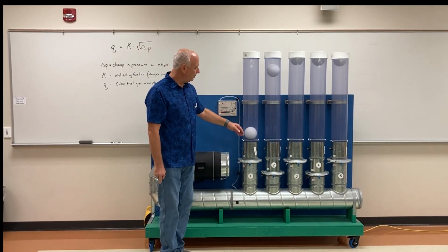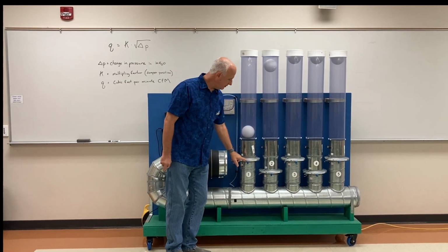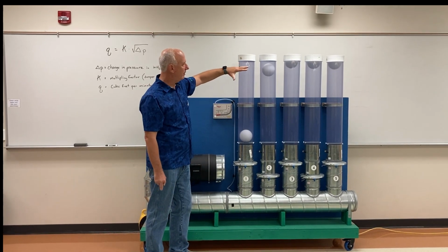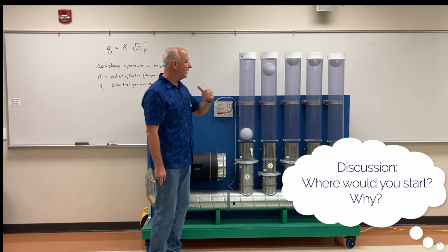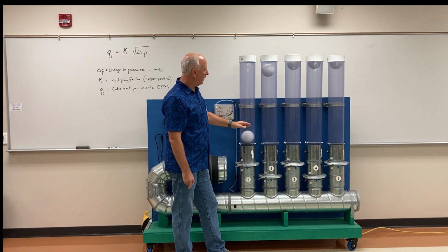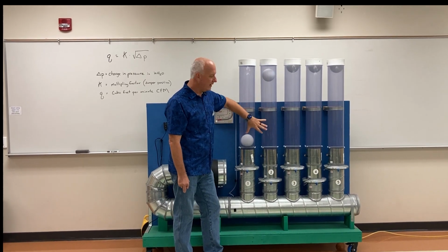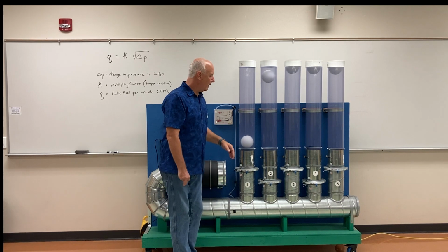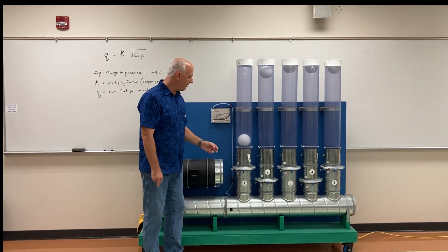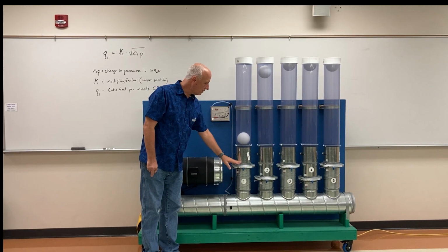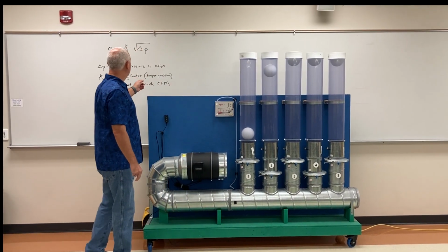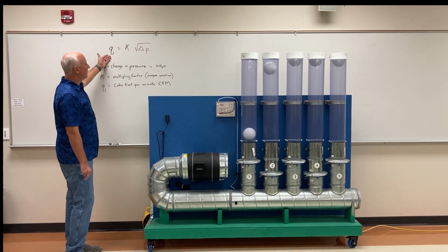So now we're going to regulate the dampers right here to get all the balls to be equal in height. And you would assume that you would start with the highest one and work your way back to the lowest one. But actually, you want to take the lowest two and get them to be equal. Okay? And just to prove what the airflow is going through here right now, we're going to check the airflow using the pressures across each damper, and I'll record them on a piece of paper.